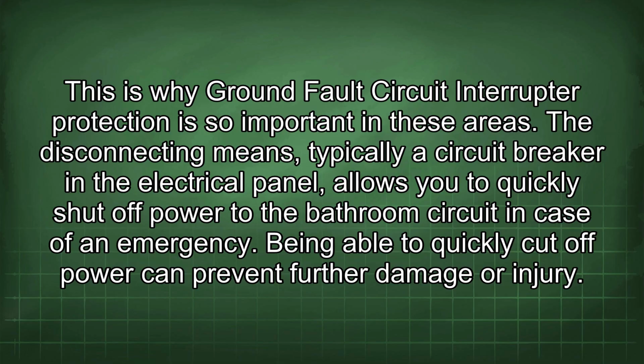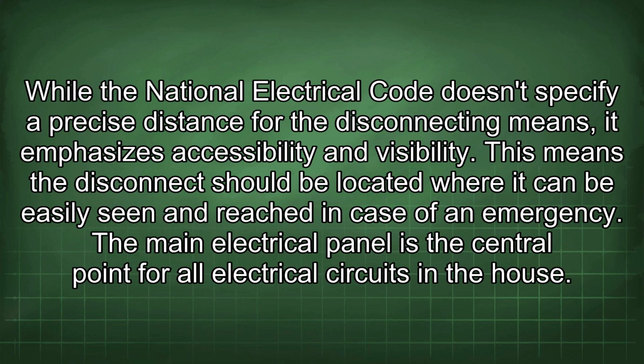The disconnecting means, typically a circuit breaker in the electrical panel, allows you to quickly shut off power to the bathroom circuit in case of an emergency. Being able to quickly cut off power can prevent further damage or injury. While the National Electrical Code doesn't specify a precise distance for the disconnecting means, it emphasizes accessibility and visibility. This means the disconnect should be located where it can be easily seen and reached in case of an emergency.